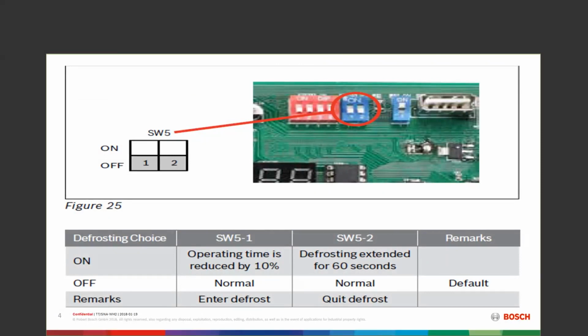One of the things that I like to bring up in the defrost mechanism is that my system's reversing valve is a B operated reversing valve. That means that I am energized in the heat mode, not the cooling mode. And so when I go into defrost, I am going to de-energize the reversing valve and then, of course, now be in the air conditioning mode.